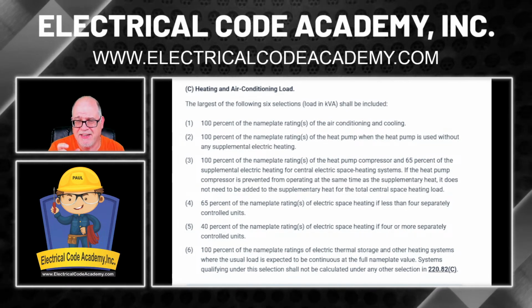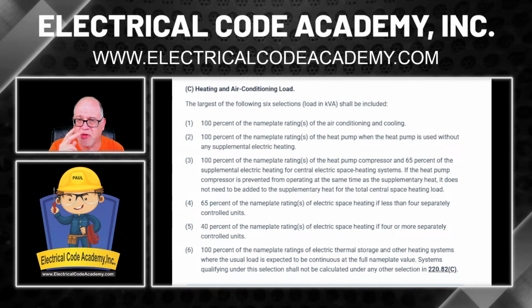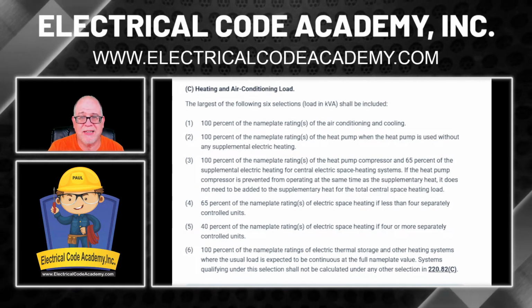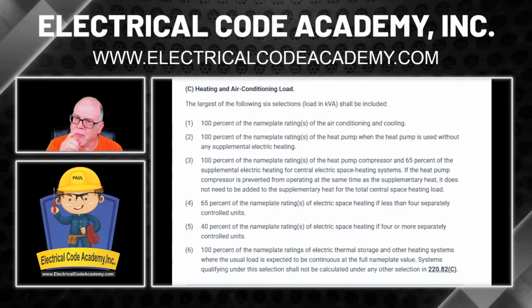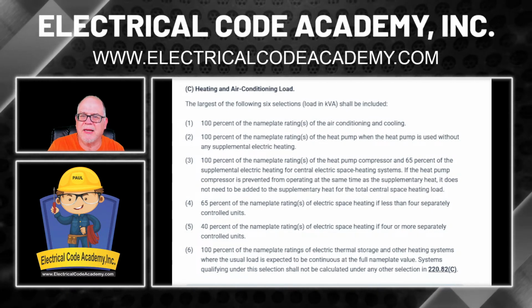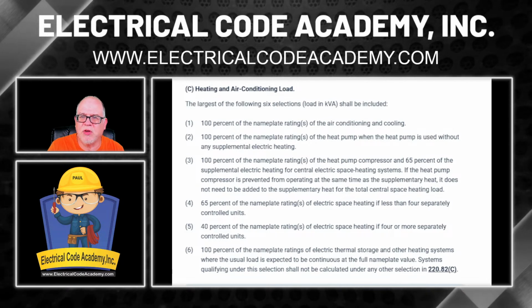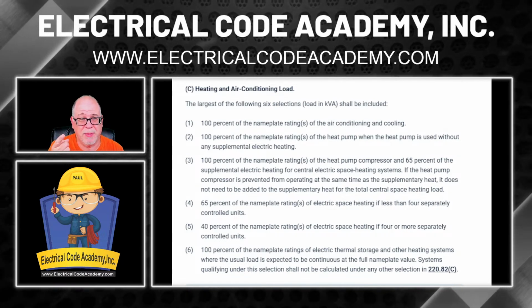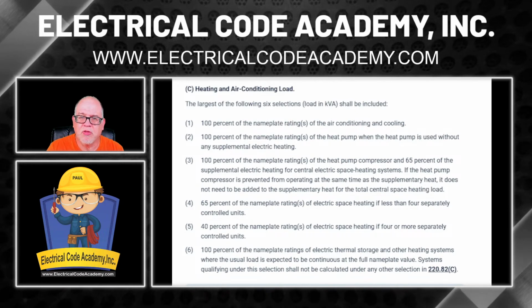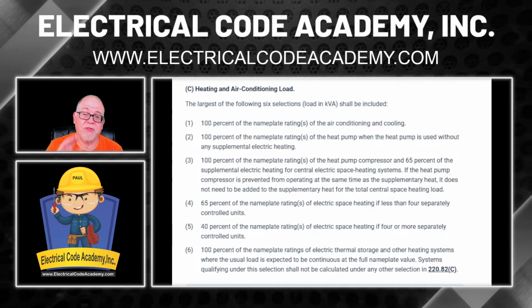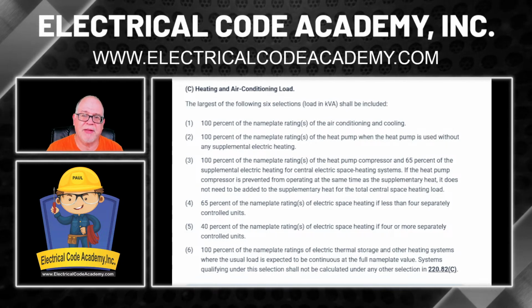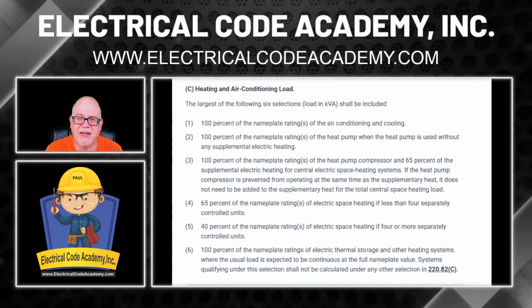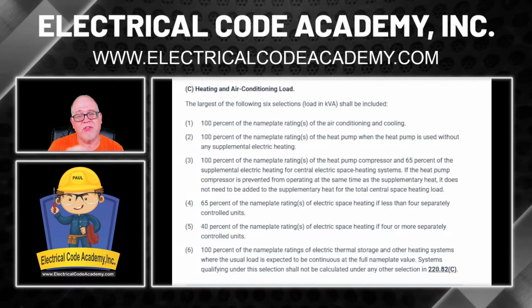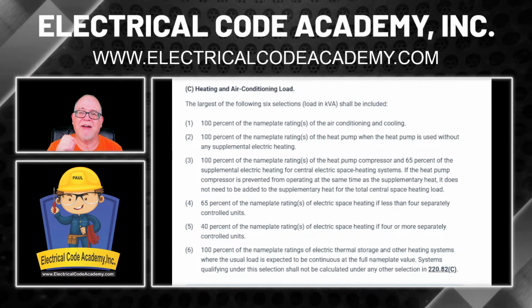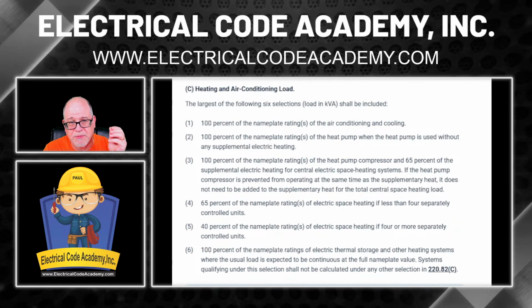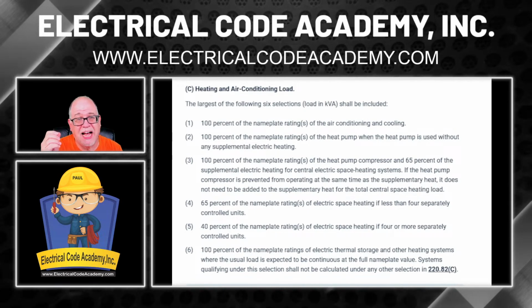Now we need to see that heat. Now, looking down the list here, the number 2 is a heat pump. Number 3 is still talking about heat pumps. Number 4, 65%. But that's electric space heating when you have less than 4. Well, we had 6, remember? We had 6. So then we have number 5. Now, 5 says 40% of the nameplate rating of electric space heating if there's 4 or more separately controlled. Well, we had 6. So obviously, we're going to be comparing number 1 for AC versus number 5 for the heat.